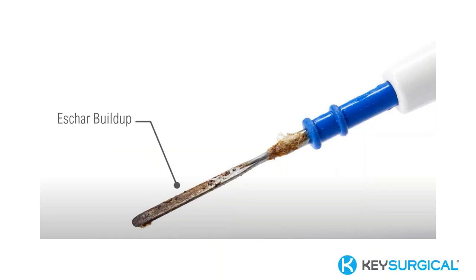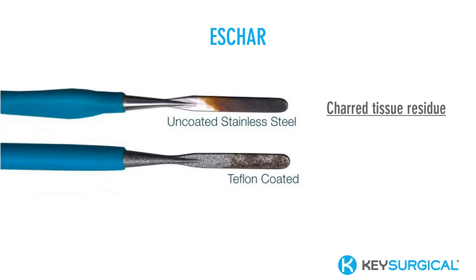So the other question that we get a lot is about coated active electrode tips. And these are not exempt from eschar either. The coating on a coated tip must be compromised for electrical current to pass through it. So you can see in the bottom picture where there are little holes in the coating. They actually have to do that in order to pass that electrical current through. So we still get eschar buildup on literally every type of instrument.